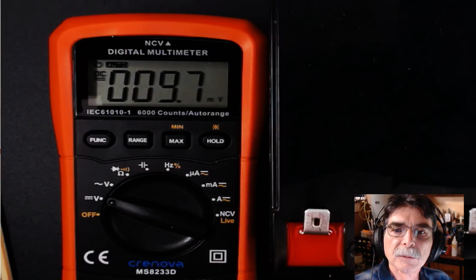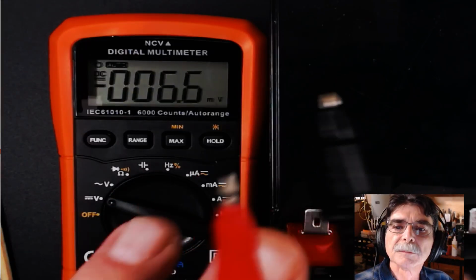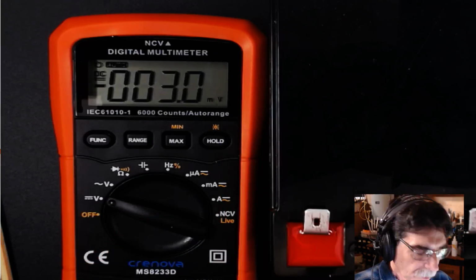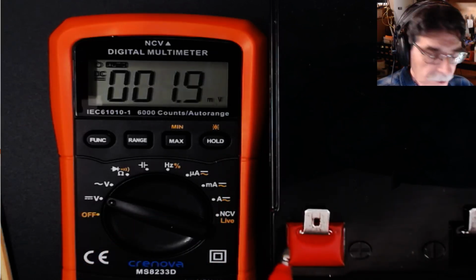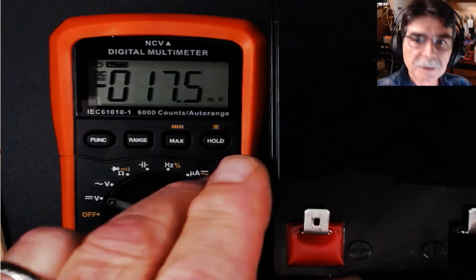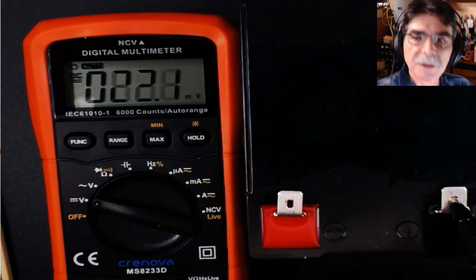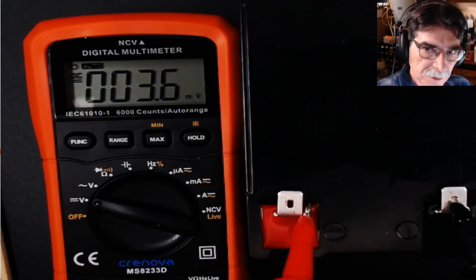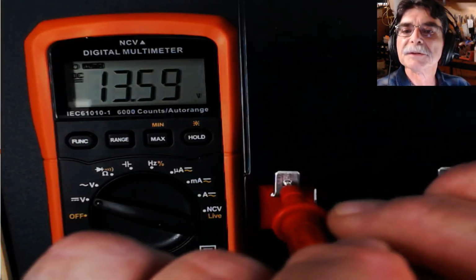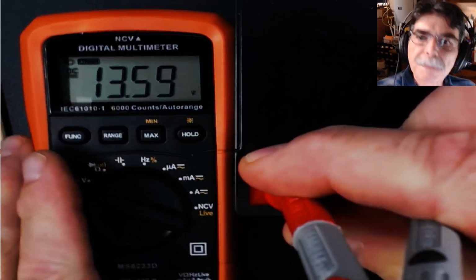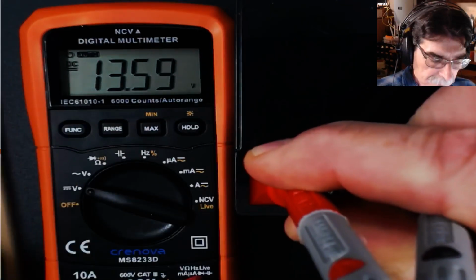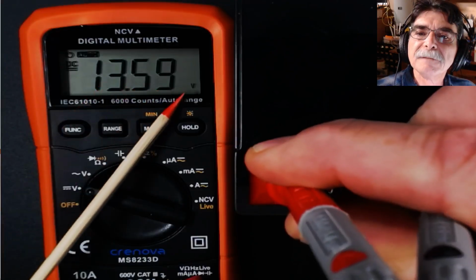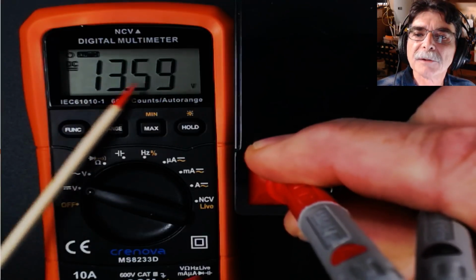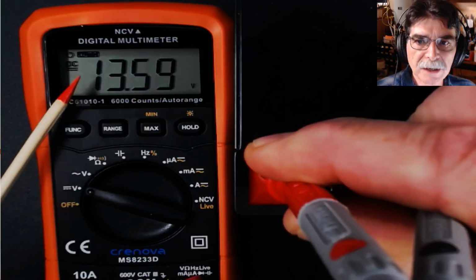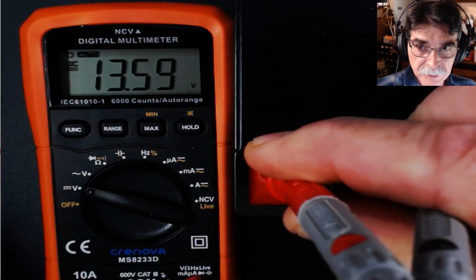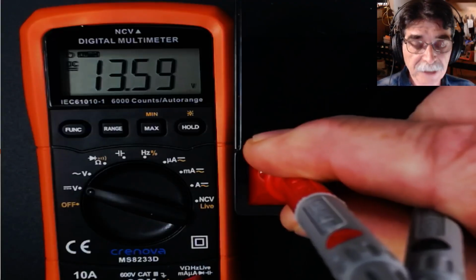Okay, so we're going to take our meter probes, black and red, and insert them into the battery post—black on the negative and red on the positive. Look what the meter says: it's telling us this battery is 13.59 volts. It doesn't say millivolts because now we're up into the voltage range, so it auto-ranged and gave us the voltage reading of 13.59.